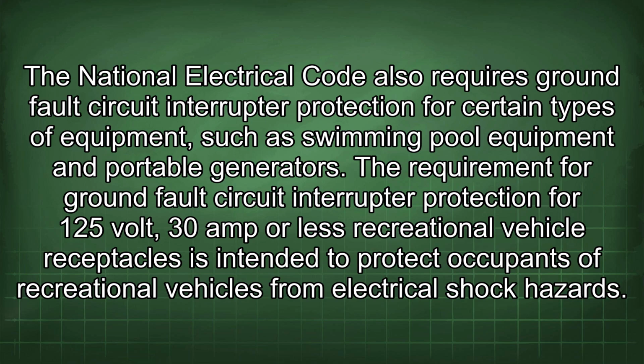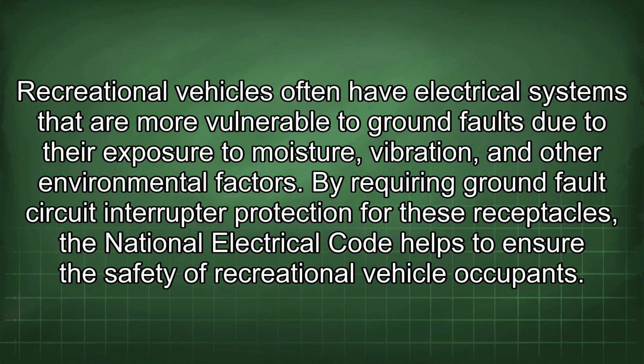The requirement for ground fault circuit interrupter protection for 125-volt, 30-amp or less recreational vehicle receptacles is intended to protect occupants of recreational vehicles from electrical shock hazards. Recreational vehicles often have electrical systems that are more vulnerable to ground faults due to their exposure to moisture, vibration, and other environmental factors. By requiring ground fault circuit interrupter protection for these receptacles, the National Electrical Code helps to ensure the safety of recreational vehicle occupants.